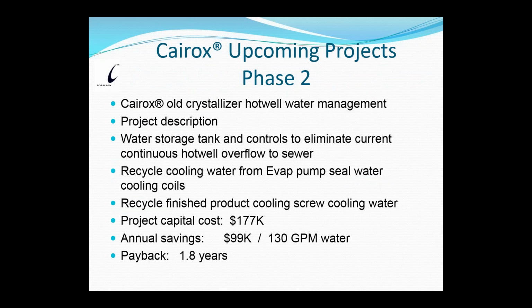So this is one project that I basically have approved that we're moving forward with. It's taking what I'd spoken about earlier, the water that comes into the old crystallizer hot well. The water just comes in at a rate, and we have to maintain a level so we don't draw below and then pump air into the crystallizer. So we're at a constant overflow rate. I measured what the overflow rate was, and it wound up being somewhere in the neighborhood of 110 gallons a minute of water just coming in, not being used at all, and going to the South Lagoon.